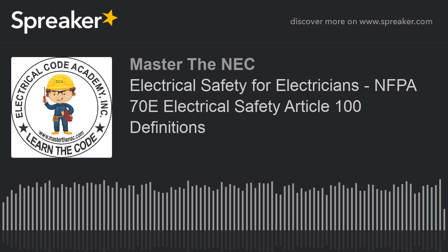Okay, now, informational note, important here. It says, Class 2 power supplies, listed low voltage lighting systems, and similar sources are examples of circuits or systems that are not considered an electrical hazard. Way important because people ask me all the time. Class 2 power supplies, again, are very limited. Listed low voltage lighting systems are very limited in the power that they can produce, so the hazards are very low. But those are examples.